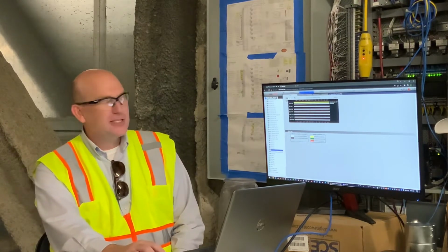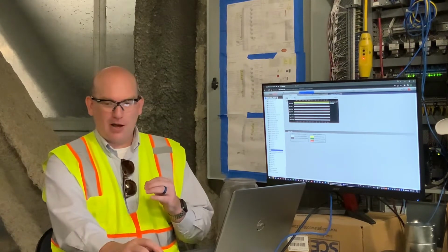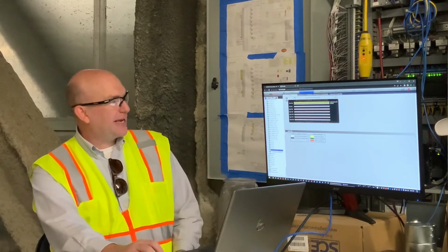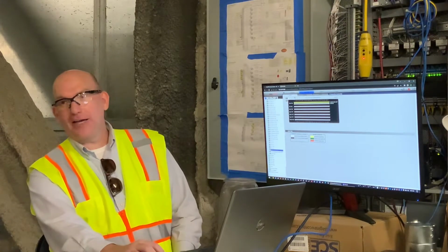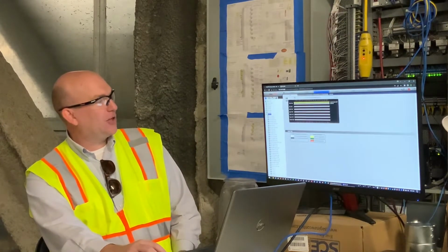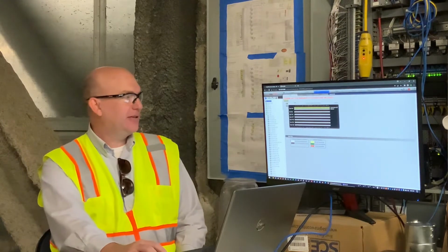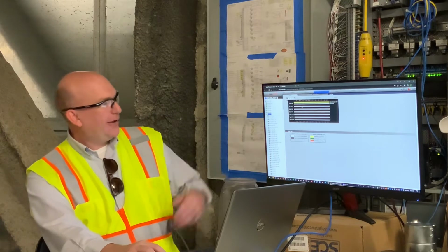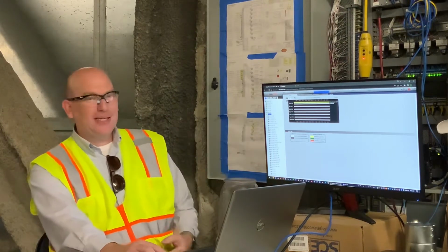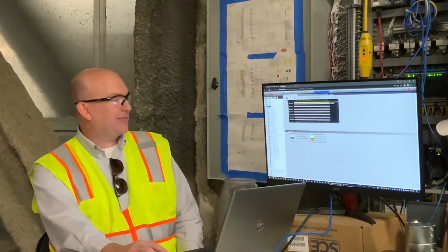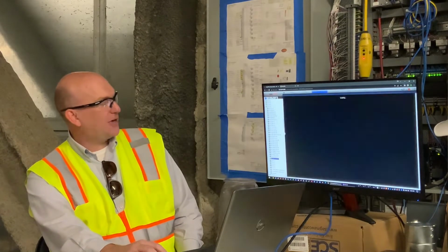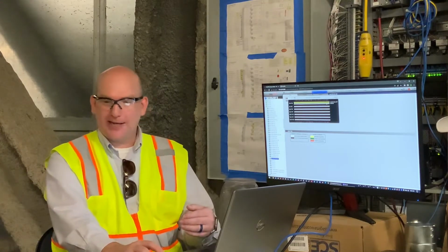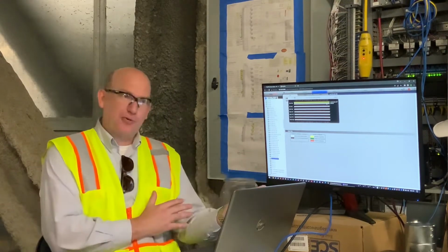But the scheduling structure for automated logic is hierarchical. That means that you can set a schedule either specifically at the device, or you can set at the location, or at the entire site. And if I set a schedule at the floor, it'll apply to everything below that floor. But then let's say there's one device I want to have a slightly different schedule. Now I can go to that device, I can click there, I can add a schedule to that one, and it'll only apply to that device, and everything else will use the previous schedule.